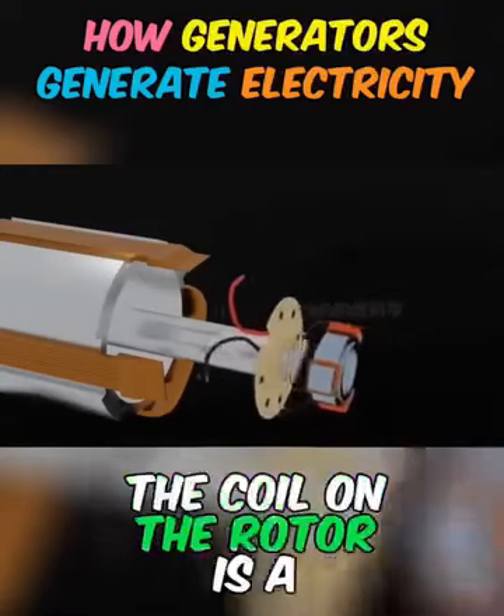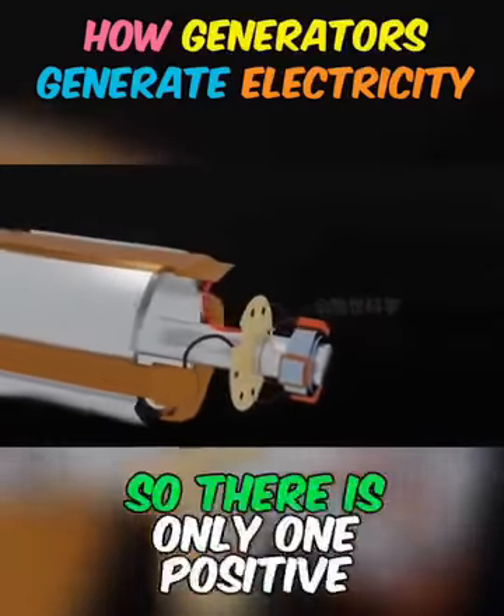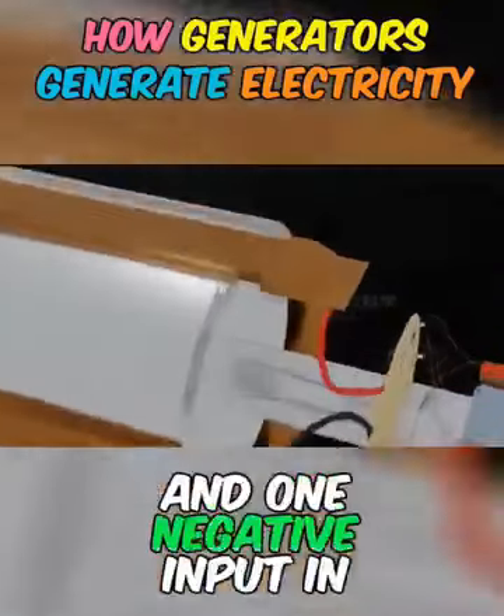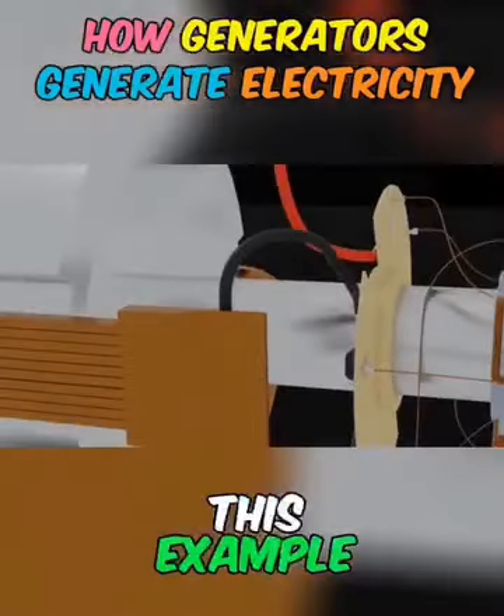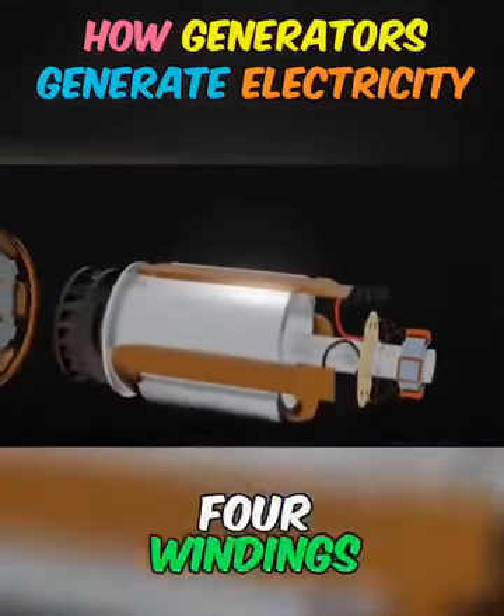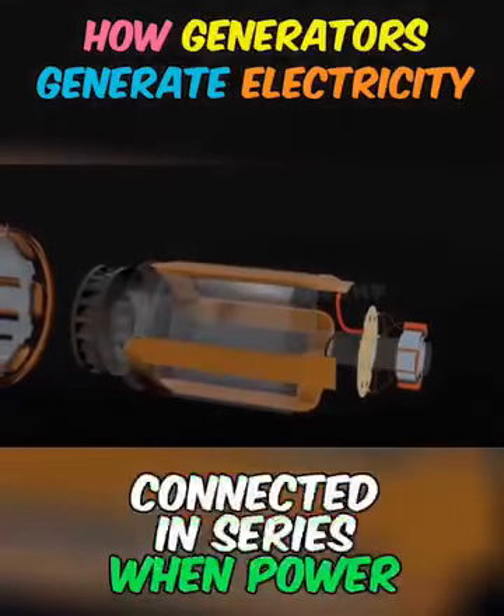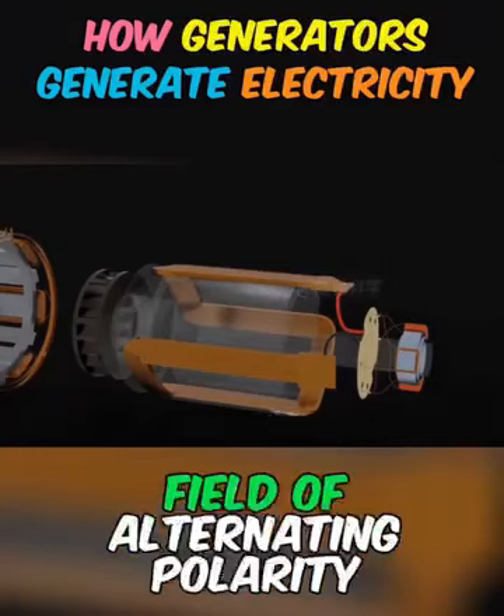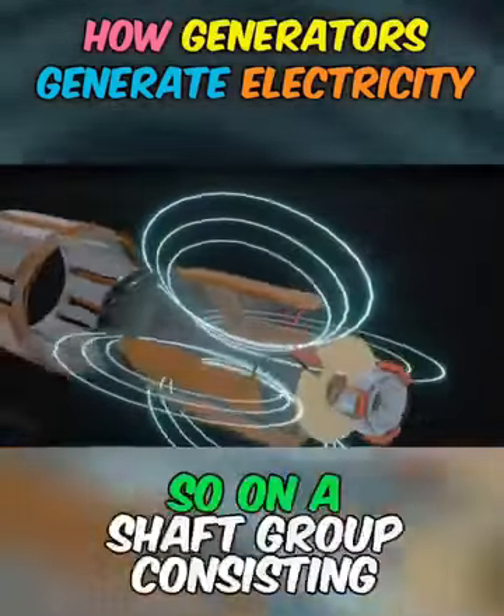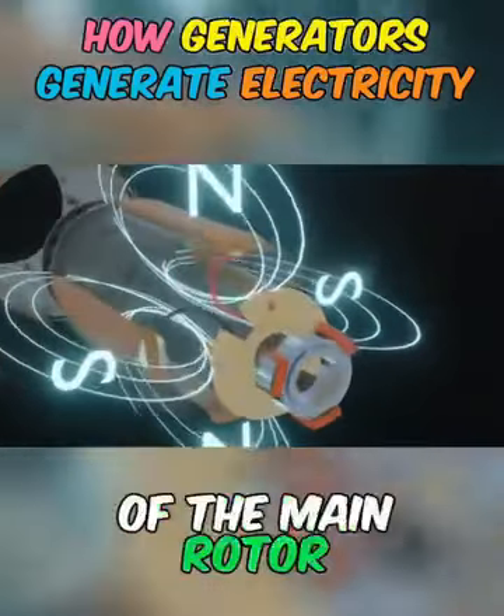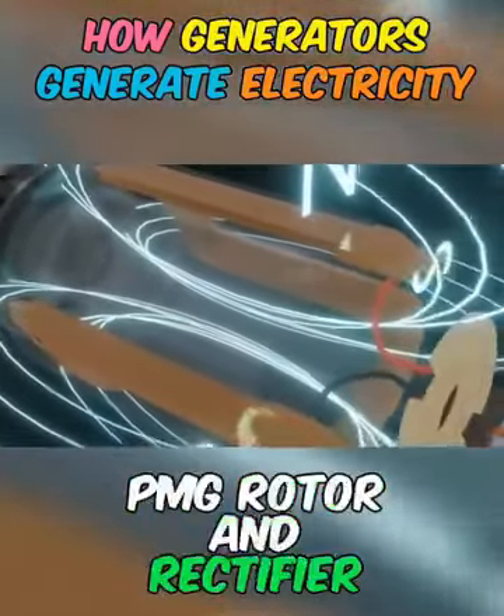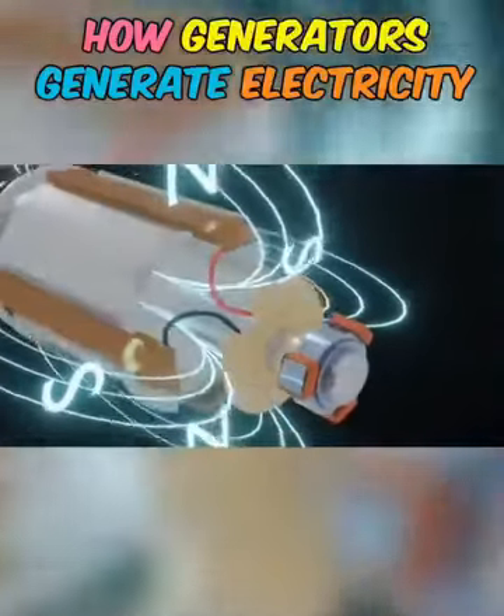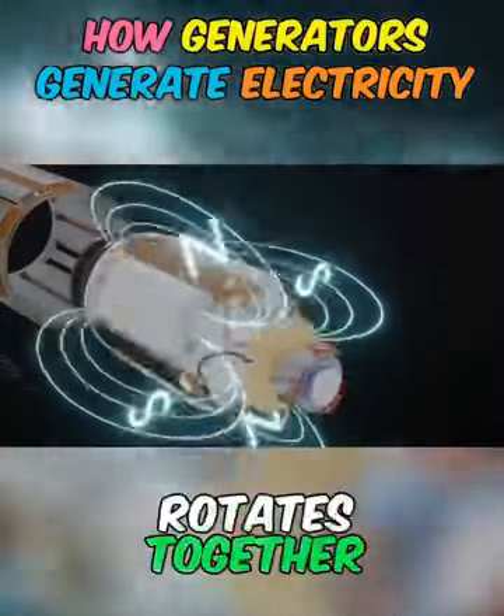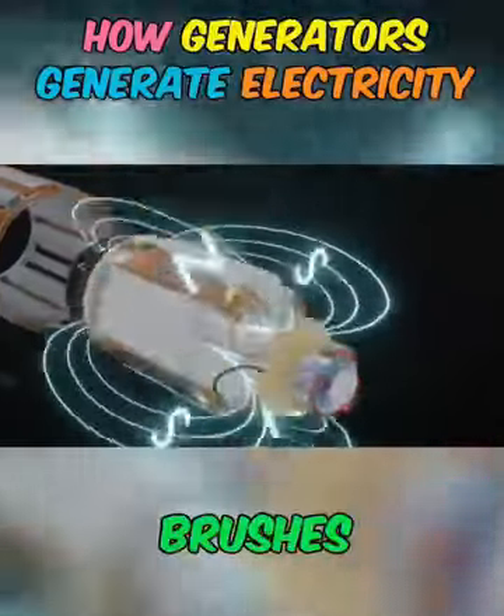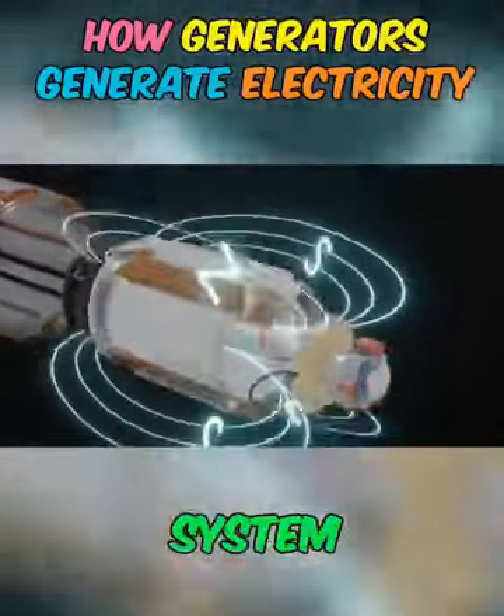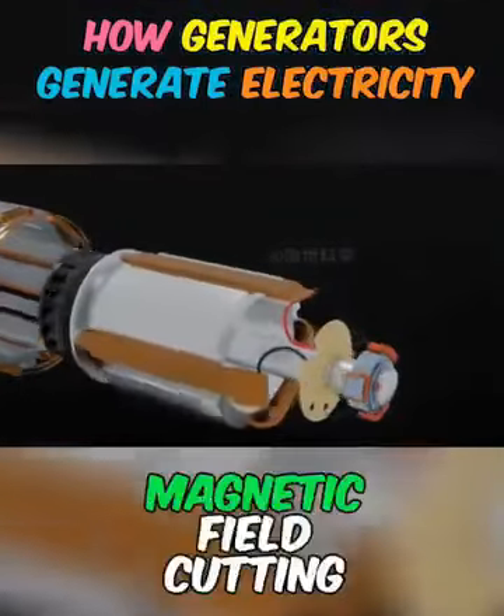The coil on the rotor is a unidirectional coil, so there is only one positive input and one negative input. In this example, the rotor coil consists of 4 windings connected in series. When power is applied, it generates a magnetic field of alternating polarity. So on a shaft group consisting of the main rotor, PMG rotor, and rectifier, the three will rotate together. Since the excitation system also rotates together, this does not require the use of brushes, so it is called a brushless system.